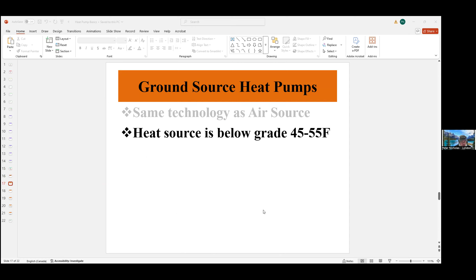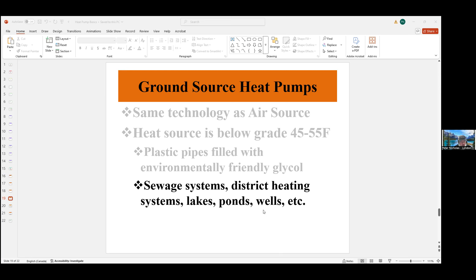Ground source heat pumps use the same technology as air source. The heat source is below grade, which is usually 45 to 55 degrees Fahrenheit. Plastic pipes filled with environmentally friendly glycol are adjacent to or very close to or embedded in sewage systems, district heating systems, lakes, ponds, wells, a trench in your backyard with those pipes in it, or boreholes. And you go down 200 feet and have a 400-foot loop of pipe in close contact with all the backfill.